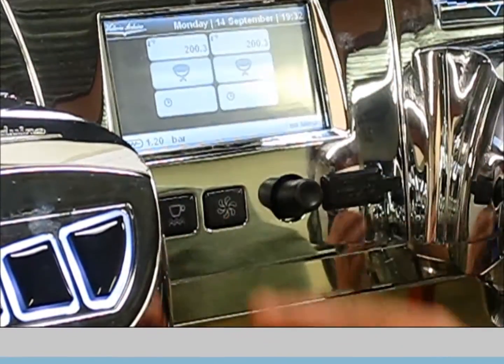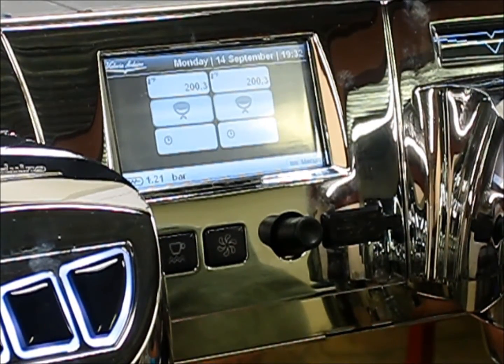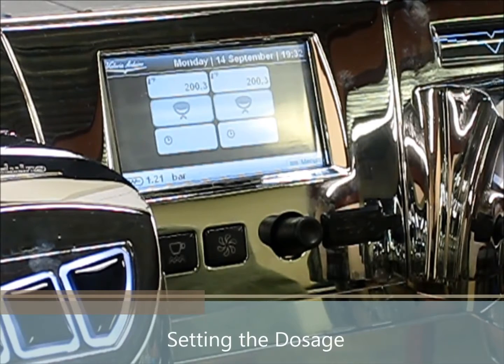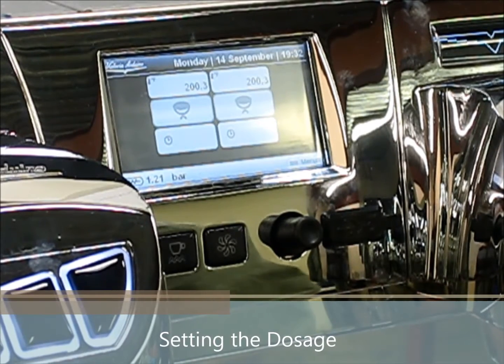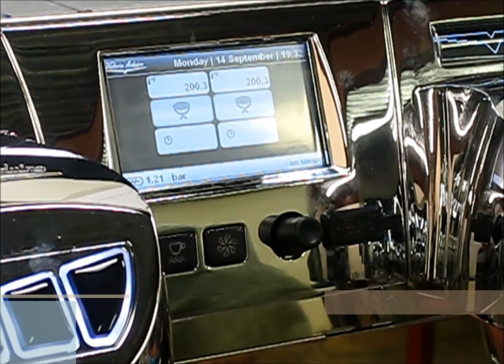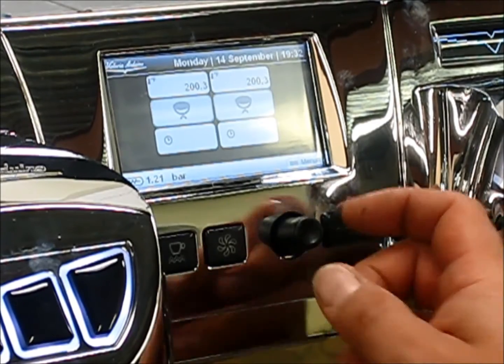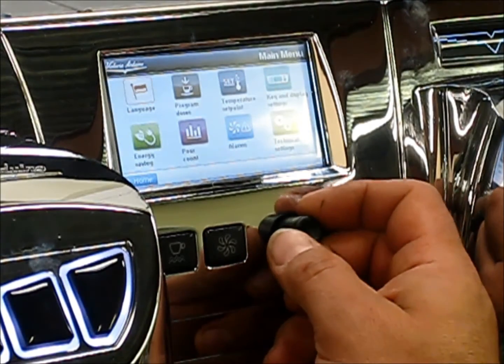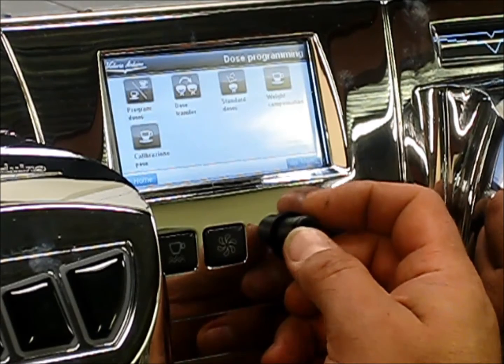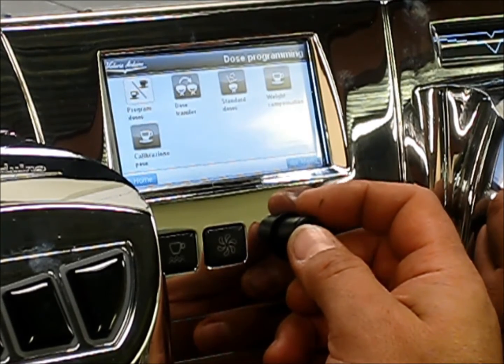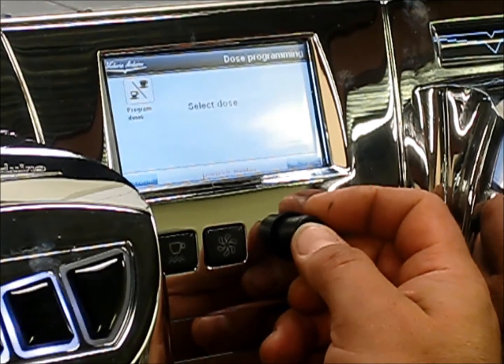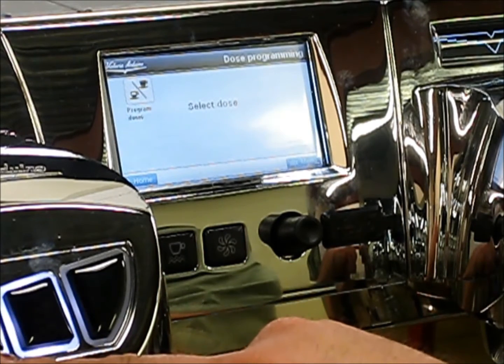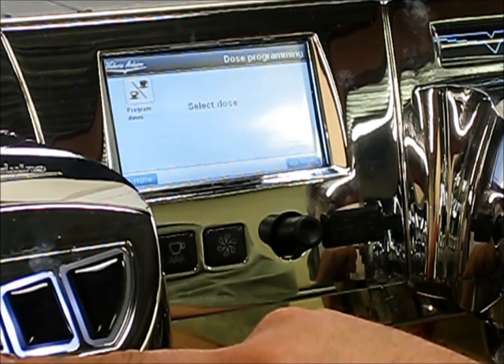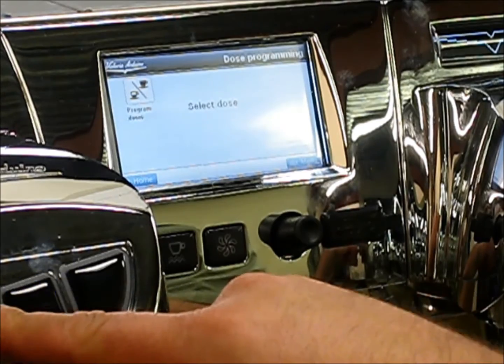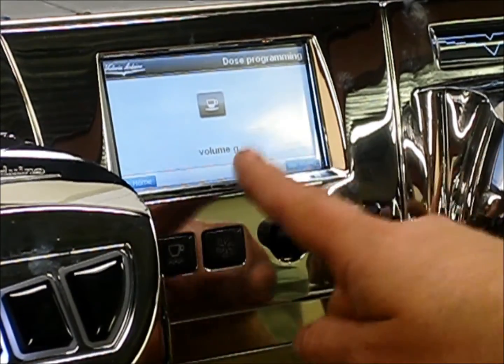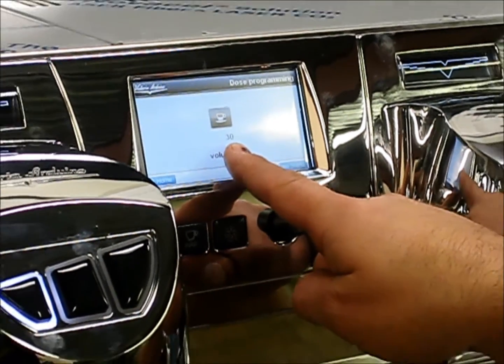We have programmed and calibrated our gravimetric scale. The next thing that we're going to do is enter programming and program the dosage in gram output for water. So what we'll do is we'll enter the menu, we'll go to program doses, highlight program doses. You'll notice that your selection for your keypads will start blinking. I will select the single measure, and then it displays a value on the screen.